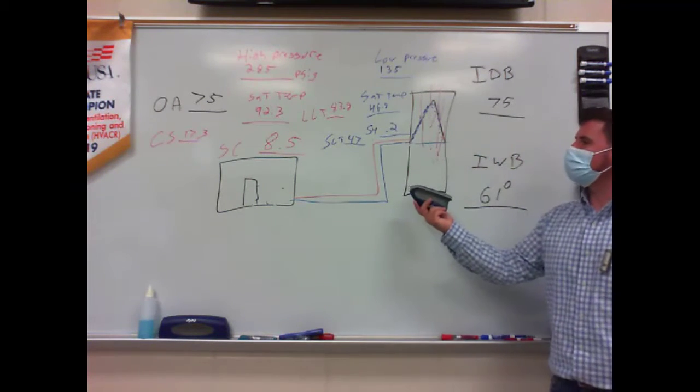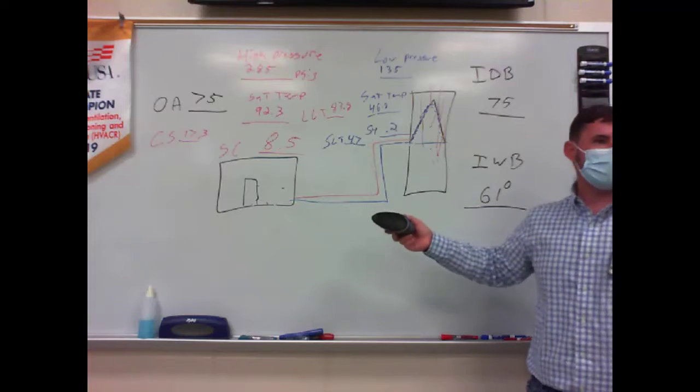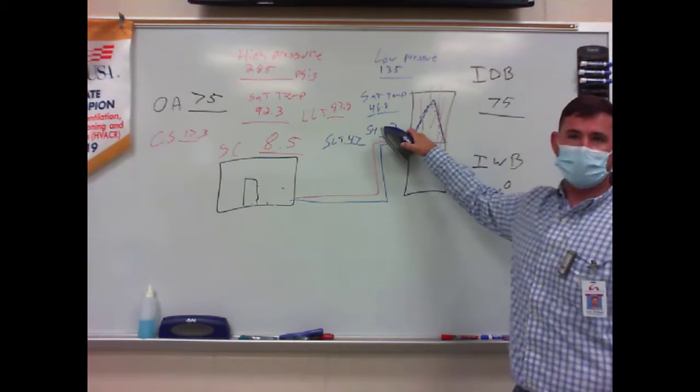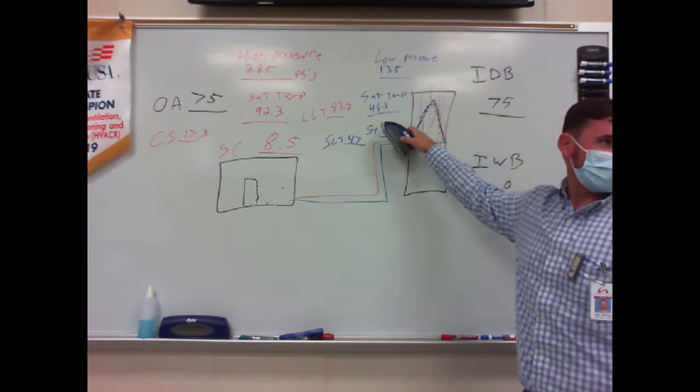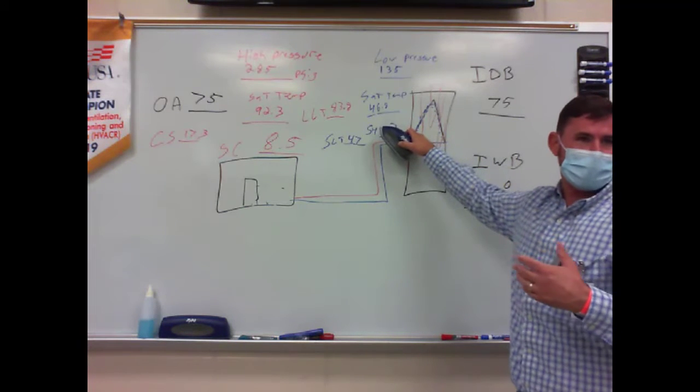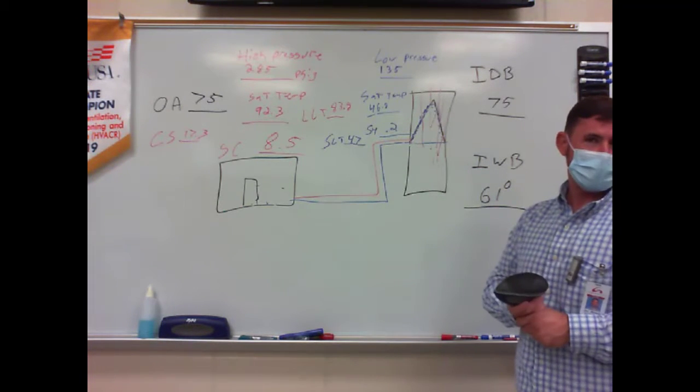So when analyzing this system, I can't say whether it's undercharged or overcharged, but I do know that my evaporator's flooding. So that issue has to be addressed first. Once I get it fixed, then I can look at my numbers and see if I'm where I need to be.